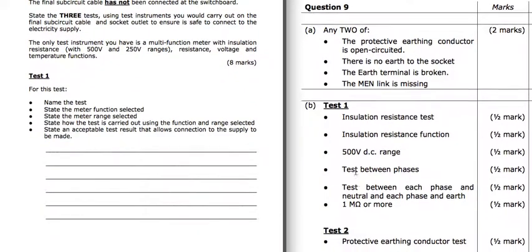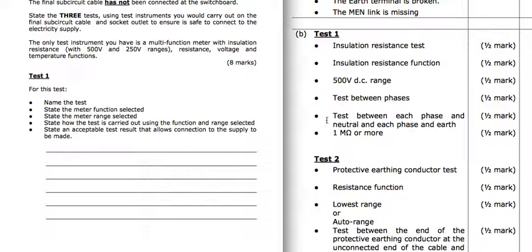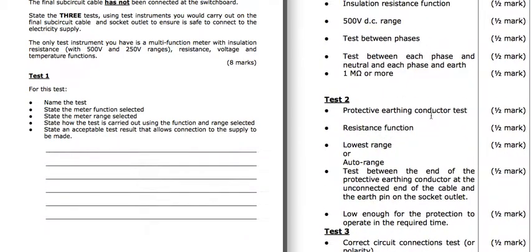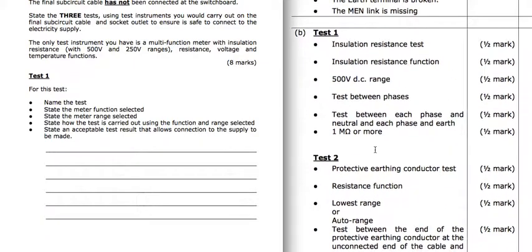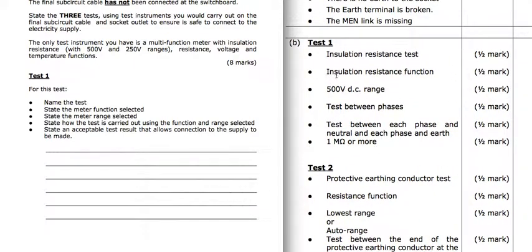So the first test we're going to do is an insulation resistance test, and the answer there, I would be tempted to do the protective earth conductor test first, but seems they've gone for insulation resistance. So insulation resistance function, 500 volts DC range. Testing between the phases, and we're going to make sure that between phase and neutral and each phase and earth, we've got 1 mega ohm or more. So you must remember that insulation resistance test, 500 volts DC, greater than 1 mega ohm.